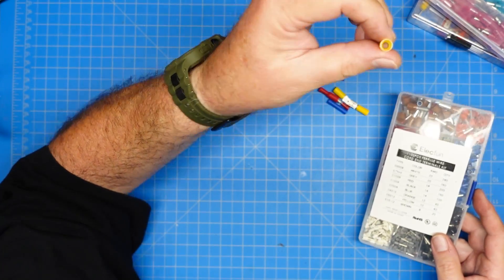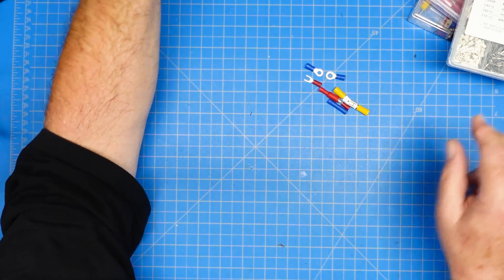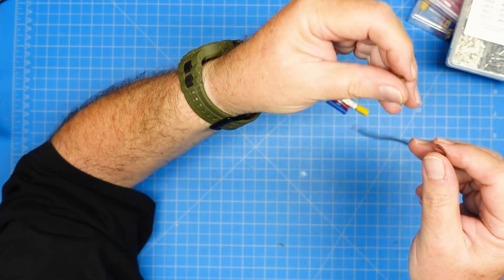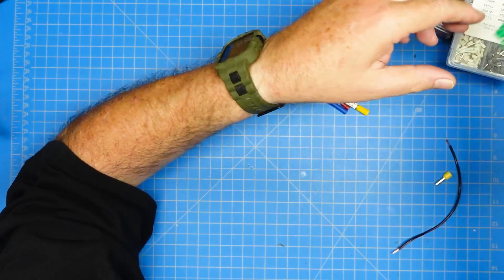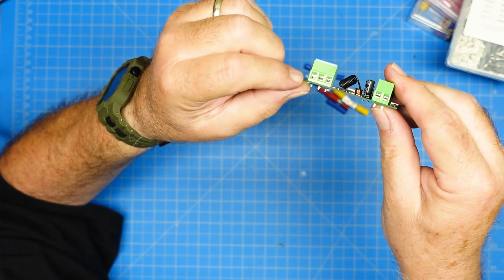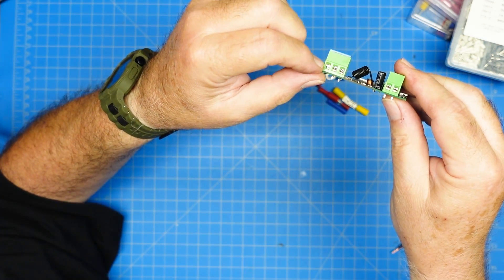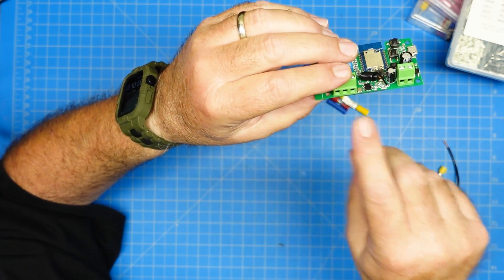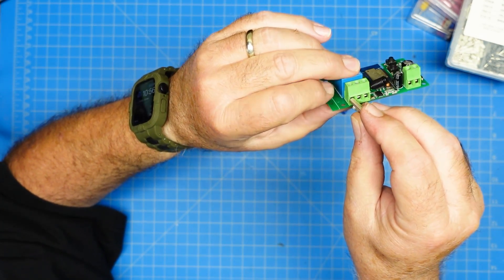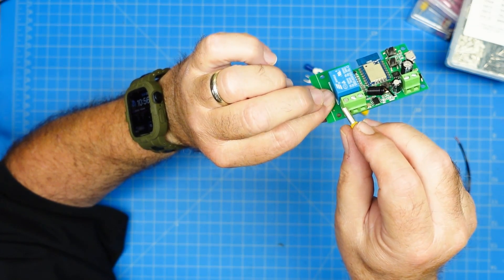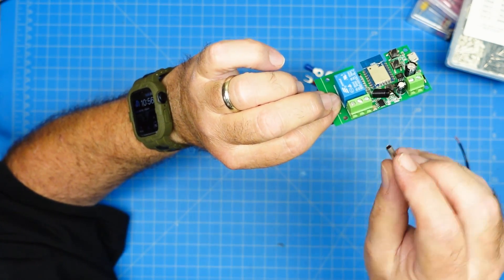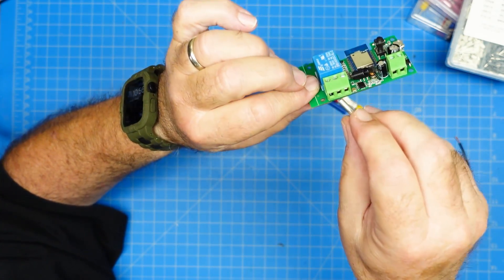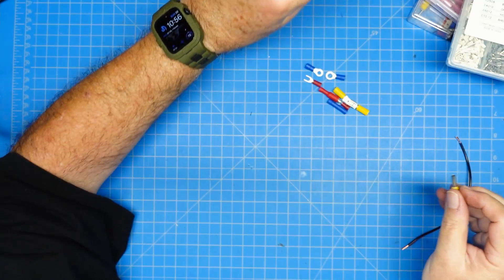So, what you do with these is the same kind of thing. You push the wire in. Now, the difference is on these, and let me get a sample wire. The difference is on these, let me back up. This is what these are typically, should be used for, is these kind of terminals. So instead of shoving a wire in there, you crimp the ferrule on the end of the wire, and you put the solid ferrule inside that and screw it down. So it should be used for these kind of screw terminal situations, because it provides a better connection. Assuming you have the right size, this is obviously not the right size for this. But that's the kind of thing that this is designed for.